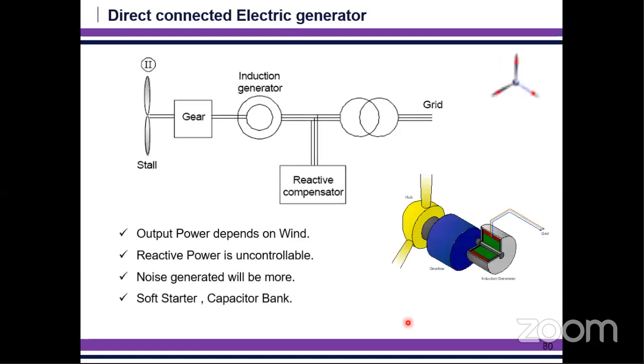So what is a direct connected electric generator was already explained, but in the picture you can understand it very well. The picture is clearly showing that the gearbox is big, and this is an induction generator, whose stator is much bigger. And even though you have the gearbox, this itself is the drawback. The gearbox is generating noise, and the reactive power is uncontrollable. It requires a soft starter or a capacitor bank. So that's another problem.